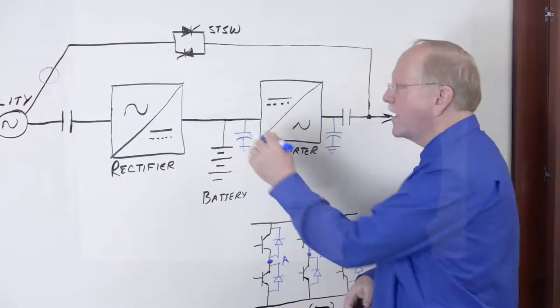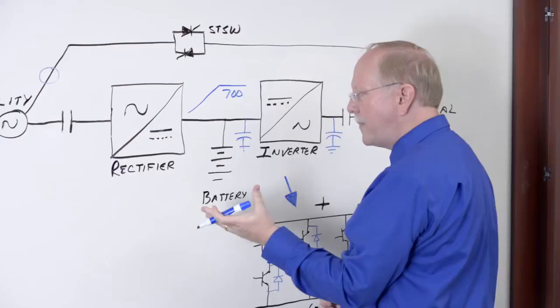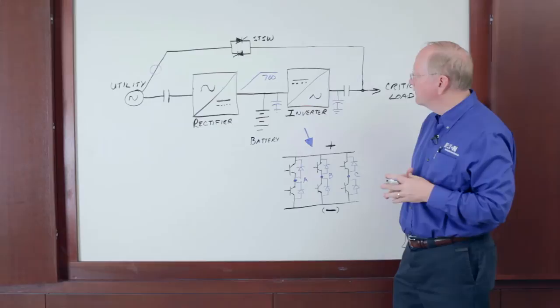How do we do that traditionally? Well, you've got to close the input contactor, you have to wait for the rectifier to ramp from zero to 700 volts DC. It's got to do that slowly over about 30 seconds or else you'll stress the capacitors connected in the DC link between the rectifier and the inverter.